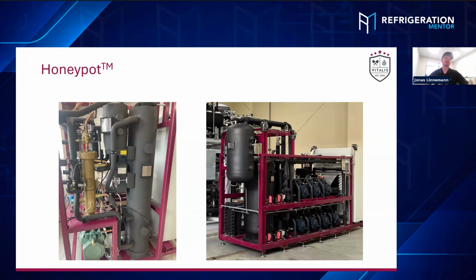I mean, ideally the oil is fairly clean, maybe with a very slight touch of yellow. Oil is not supposed to be dark brown, also seen many times. Also, if you do a filter change and you smell that the oil smells like burnt plastic, I think everyone in the field has recognized that at some point. That's never a good sign, and that is an indicator to perform a complete oil change at some point, because you want to have the oil just as clean as possible.